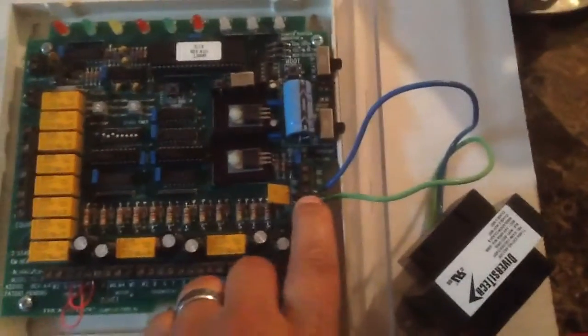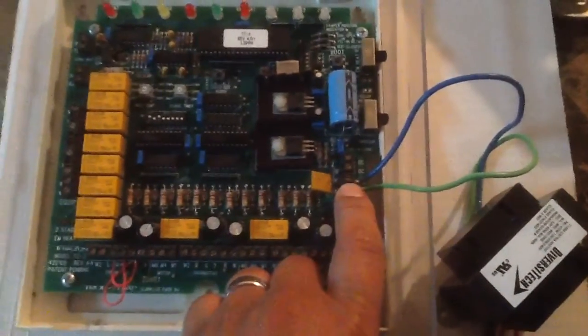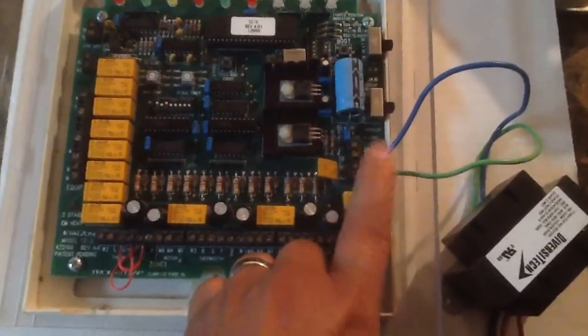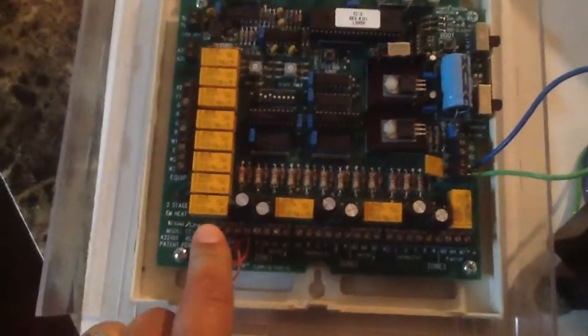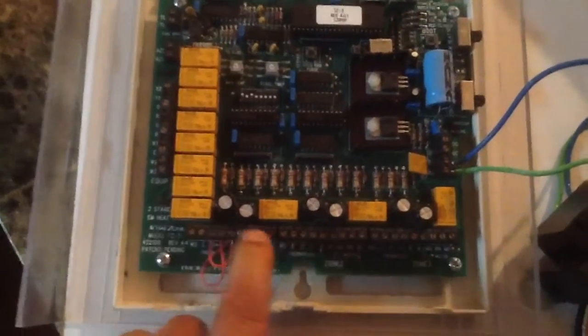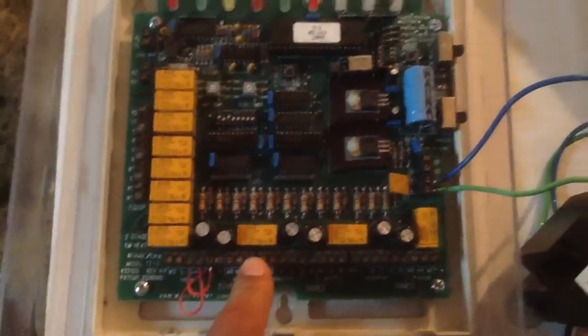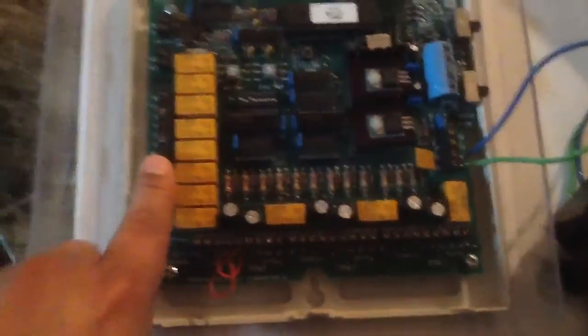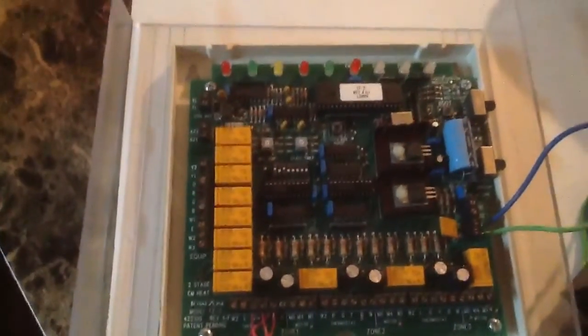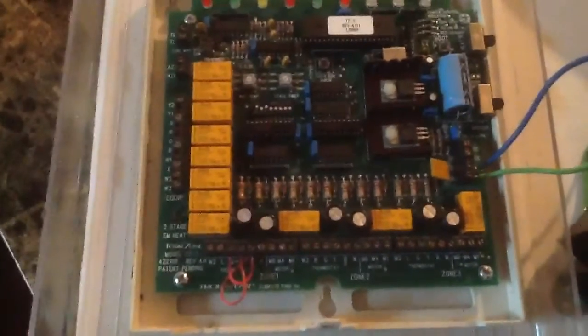If everything's dead in here, you want to check for 24 volts. That's the first thing I always do when I troubleshoot. I check right here. If I've got 24 volts, then I move on to the thermostats. If I'm good there, then I move on to the dampers, make sure the dampers are functioning, and then I move on to the equipment. And if I don't get that, like in this case, I wasn't getting any output between common and W1, then it's a bad zone board. Now, if you are getting an output, then you move on to the equipment. You just have an equipment issue.